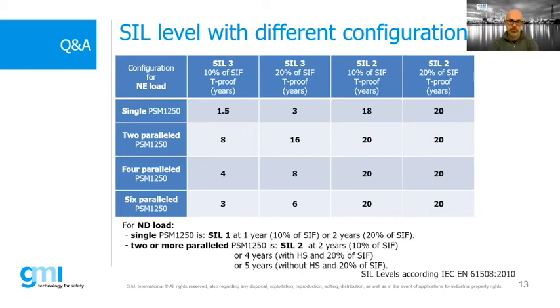If that same power supply, in the second square here, is working at 20% of the SIF, the proof test is valid for 3 years. So you can keep on working that power supply for 3 years. If you use a SIL 3 device, a direct device, you can use it for SIL 3, of course, but you can also use it for SIL 2 application. No issue for that. If you use the same power supply at 10% of the SIF in the SIL 2 application, the proof test time will be valid for 18 years. If you use it at 20%, it will be valid for 20 years. 20 years is, let's say, the lifetime of the device, so that is the stop at 20 years.